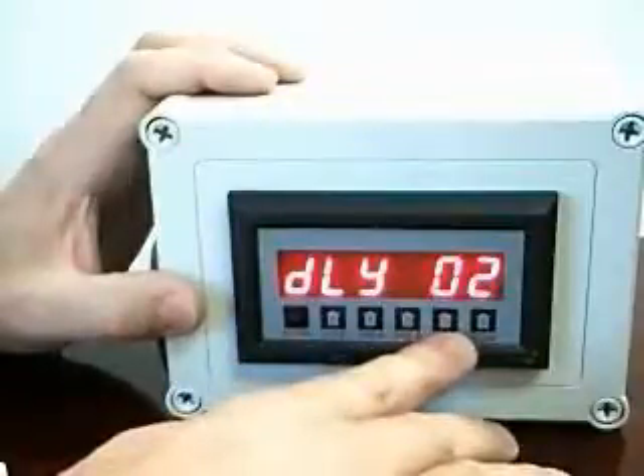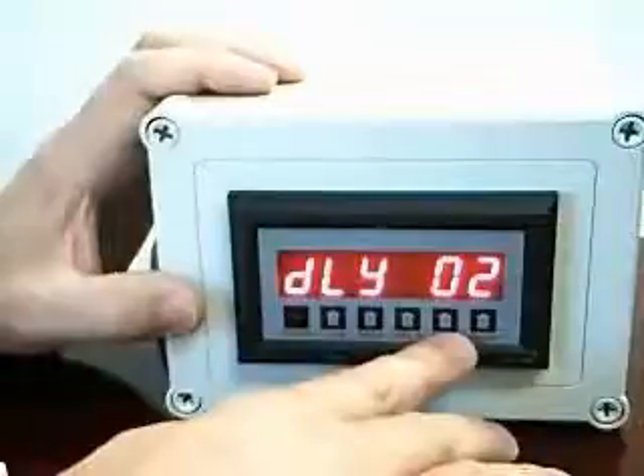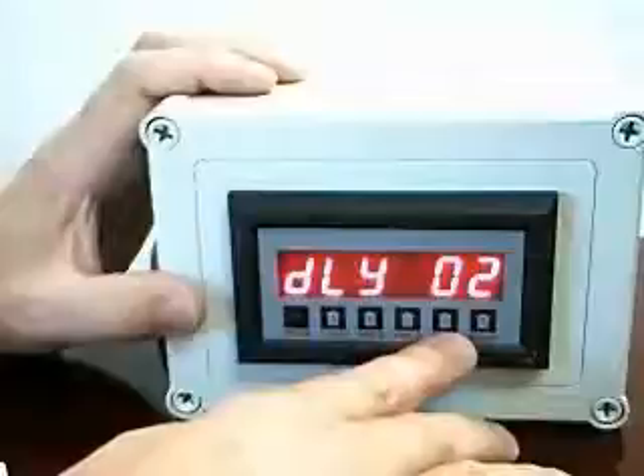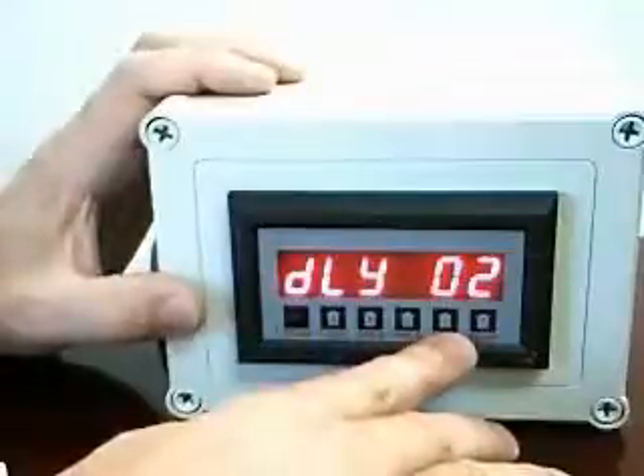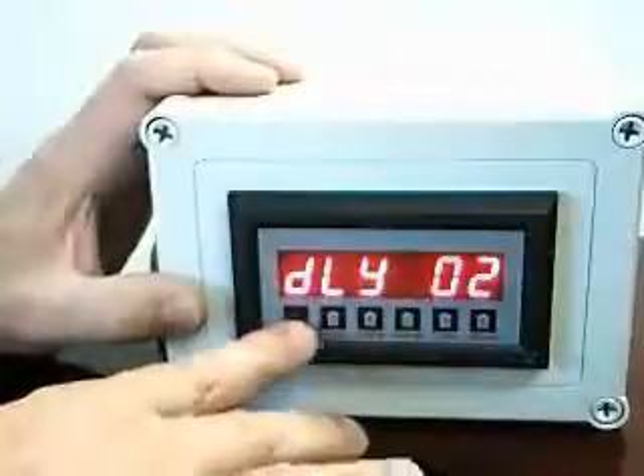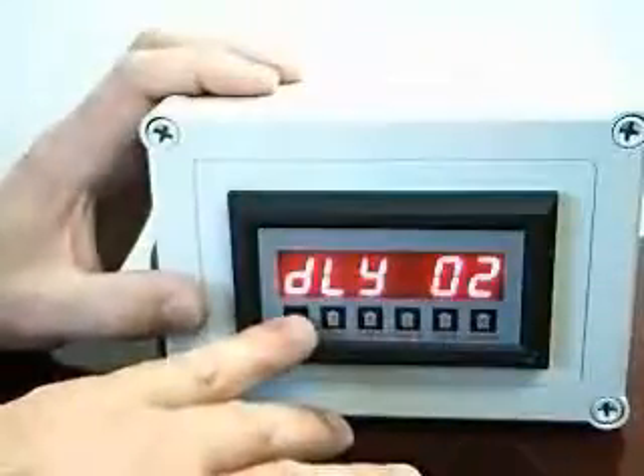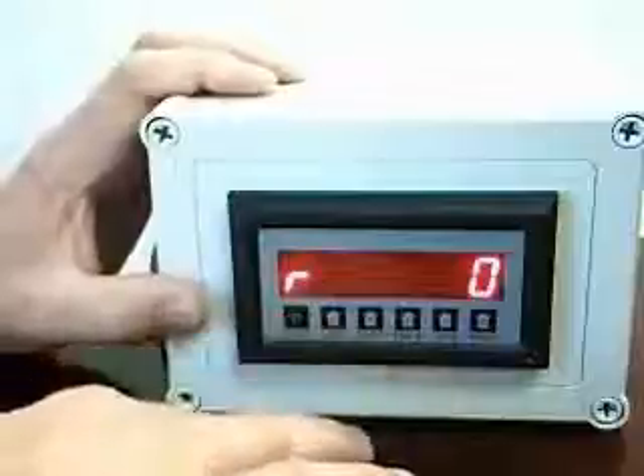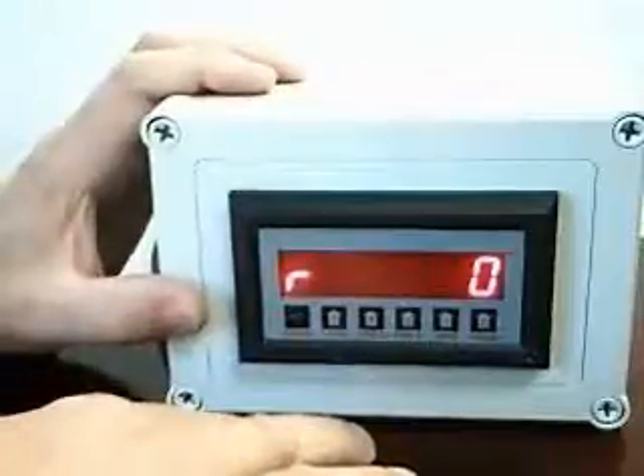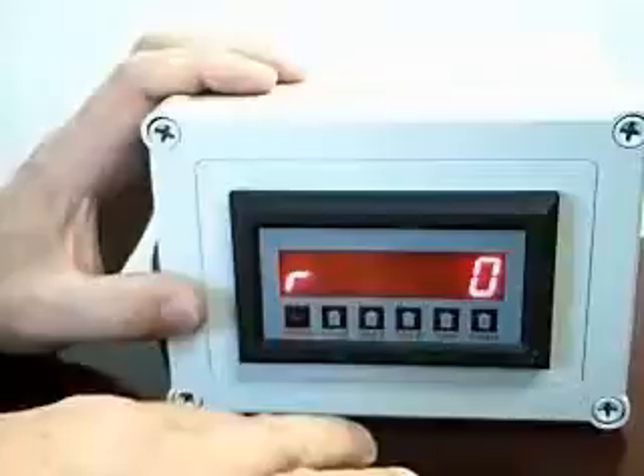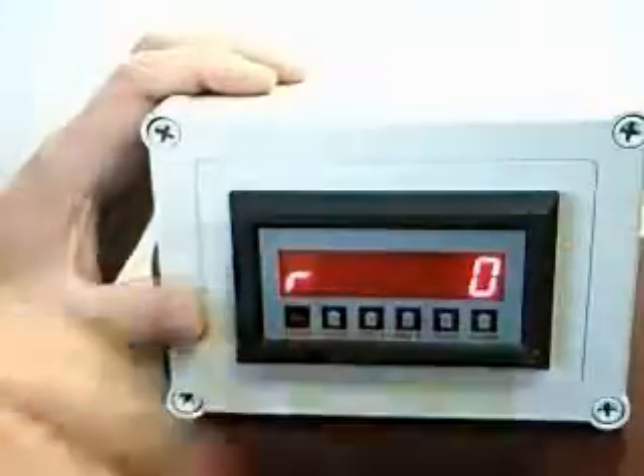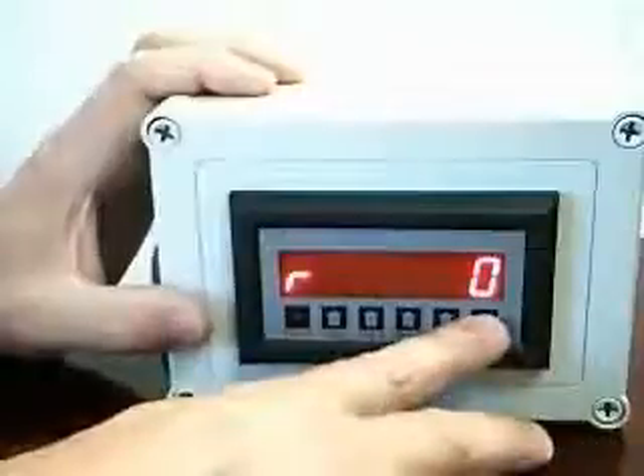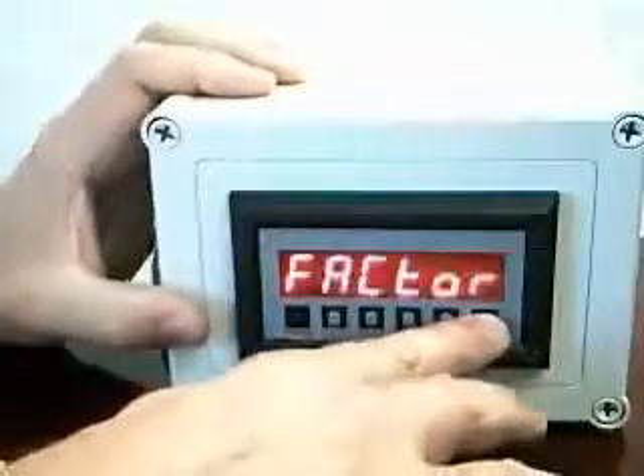This is typically used with contact closure inputs that have slow repetition rates at low flow to advise the instrument to wait a longer period before assuming that the flow rate is 0. I'm going to leave it with the default setting of 2 seconds. That completed the setup of the rate submenu group, and the unit returned to the run mode. Let's go to the next menu location.